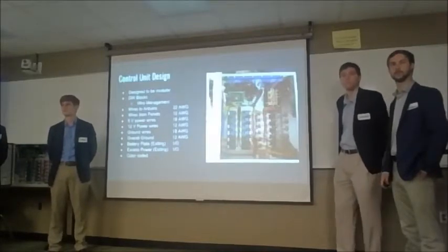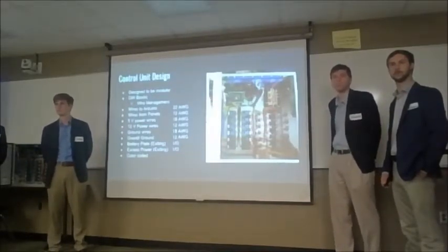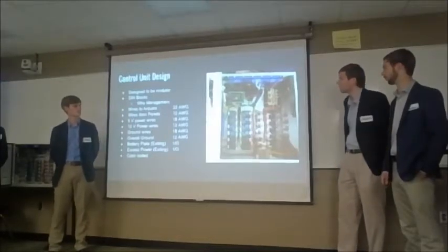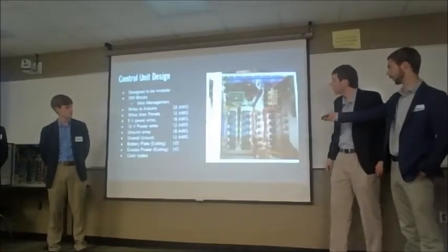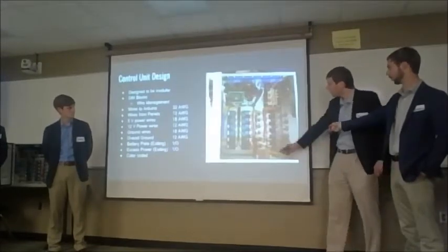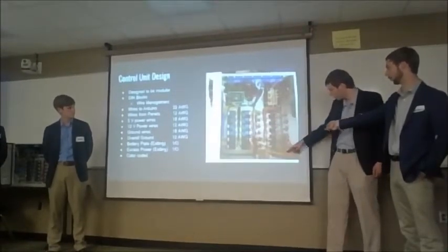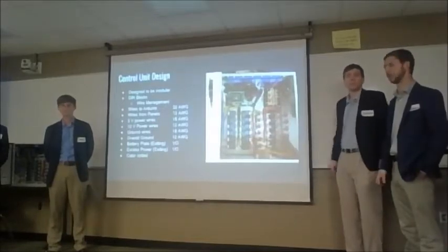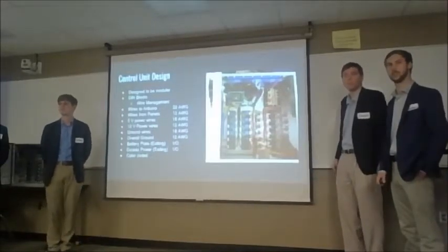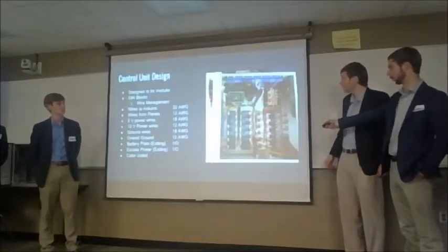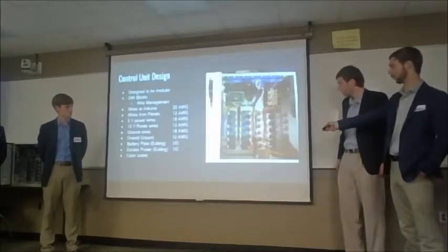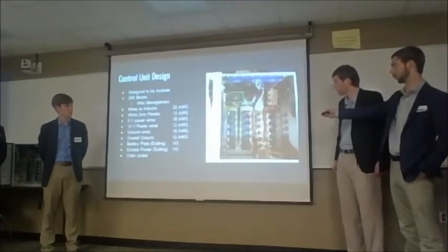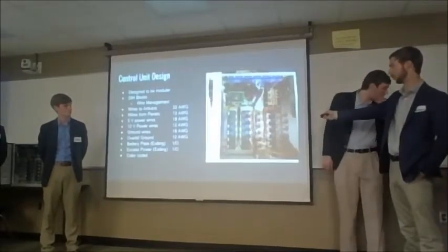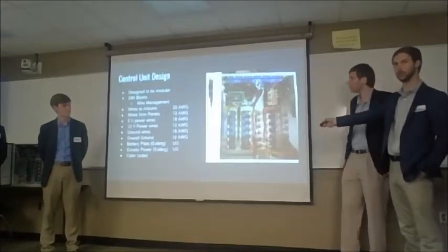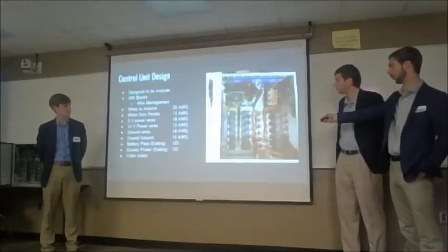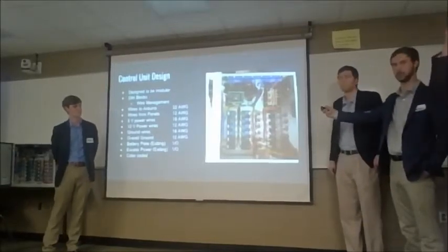And like in your example where you take panel 2 offline, does panel 3 then become panel 2? No, they have consistent numbers - we've got R6, 5, 4, 3, 2, 1 corresponding to panel inputs 1 through 6. Usually one will turn on first, and then they go in order. So if 6 is on, 5 through 1 are also always on. If 4 is on, 3, 2, 1 are always on, but 5 and 6 could be off.